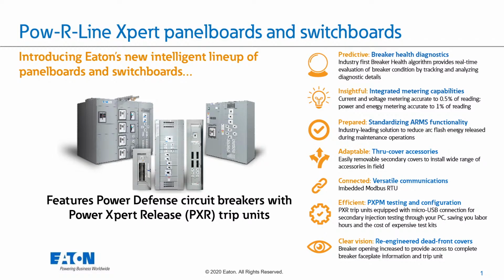You think about all of those widgets that you have to install in assemblies or maybe external to the assembly in order to meter branch circuits. A lot of connection points, a lot of different devices that are connected together, but now we have built-in metering into the trip units that removes all of that clutter and extra devices that are needed to meter at a branch level. We have standardized ARMS functionality, ARMS being the Arcflash Reduction Maintenance Switch, which we'll also talk about here today.